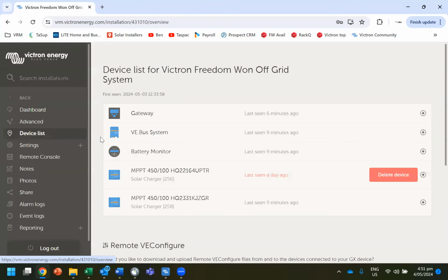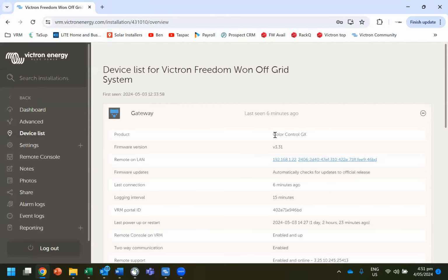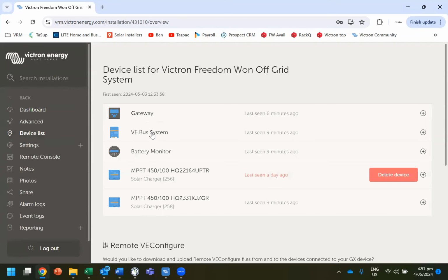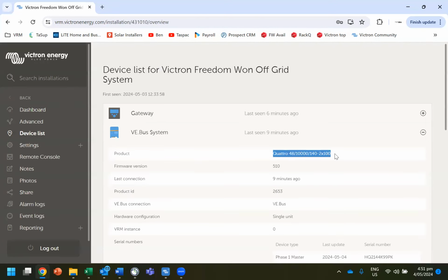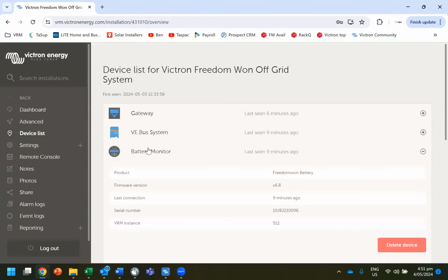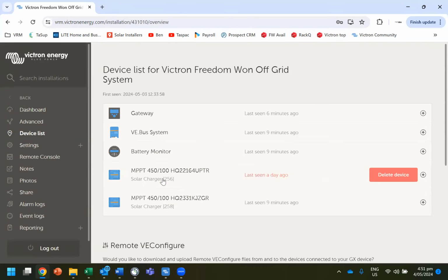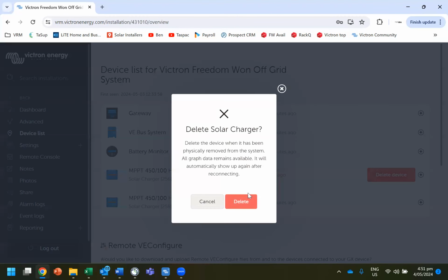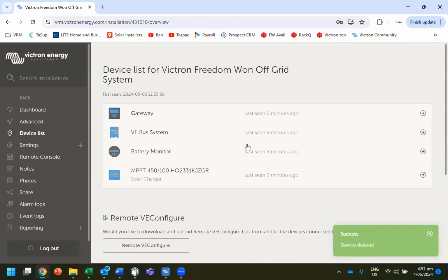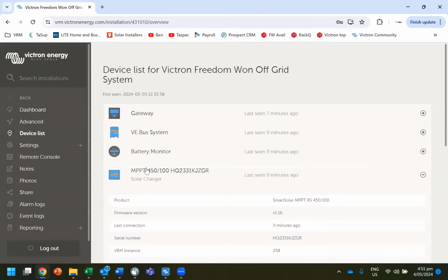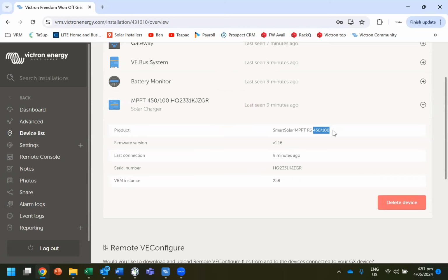So if we look at the device list, we've got a Color Control GX and we've got a Quattro 10. So it's 48 volt, 10,000 VA, or watts, if you are simple. And we've got a Freedom Won battery. And we've got an old charge controller, which looks like it might have been a different device. So I'm going to delete that. If it comes back, then it will show up again. So there's no problem deleting it out of this list. I've got a charge controller there, which is a 450-100.